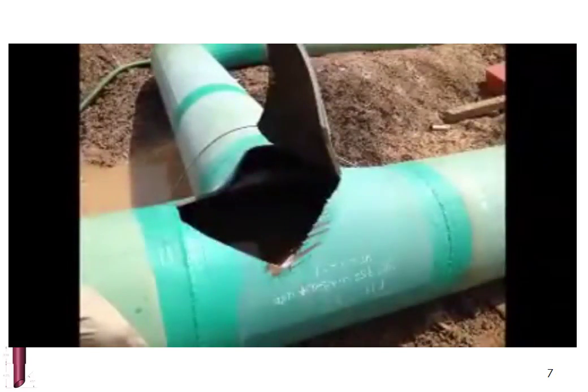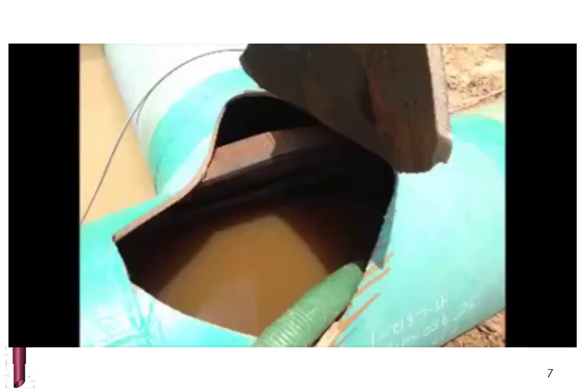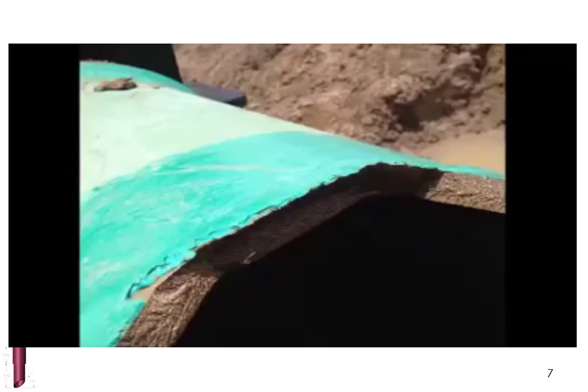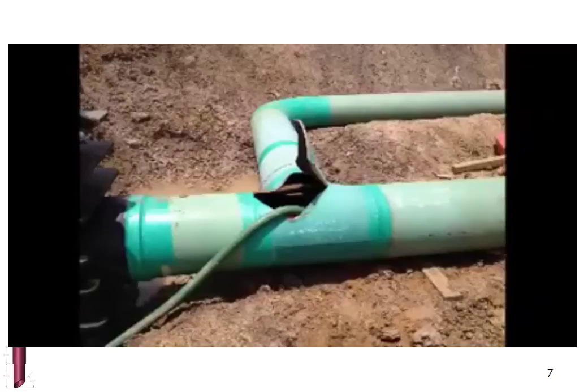Here's what we're looking at. We're looking at 3/8 inch wall thickness pipe that just peeled back. I think it's a 26-inch line, and it's standard wall. So you're seeing a lot of mass, a lot of metal mass ripped away. That's a lot of force that took place in that piece of pipe, especially when you think the pipe is curved, so they had to overcome the resistance to bending of that curve.